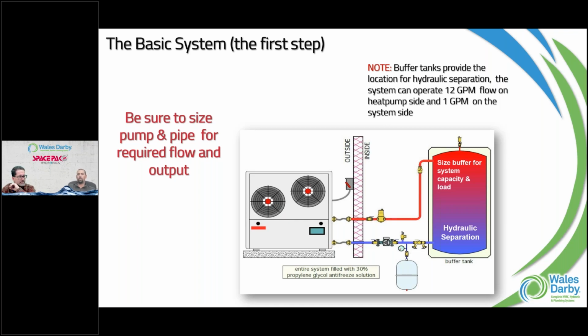With a VRF system, if you wanted multiple indoor units in the mini split world, one in heating, one in cooling, you had to have them on two systems or wait to figure out which one you wanted. With air to water, we have that flexibility too, where if you're good with piping and understand it, with the addition of 3-way valves and stuff like that, we can have a heated tank and a chilled water tank.